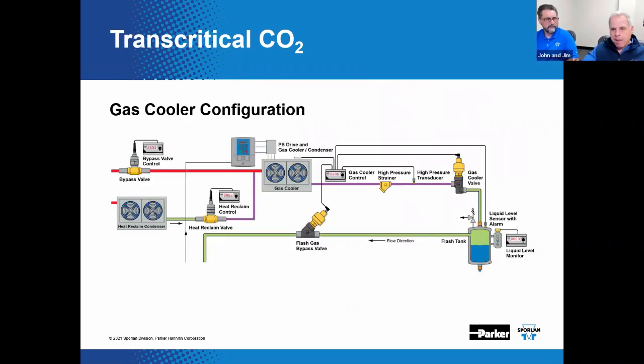Right. Do that compression in steps, essentially. Here is the gas cooler configuration or arrangement. The heat reclaim and bypass valves are used to control the heat reclaim process in a similar manner to any HFC DX system. This otherwise wasted energy could then be used to heat the store or to heat domestic water. The gas cooler simply helps to reject heat to the ambient, and that's what we see going on right here. So it's a dry cooler of sorts. And it's essentially a sensible heat transfer process.